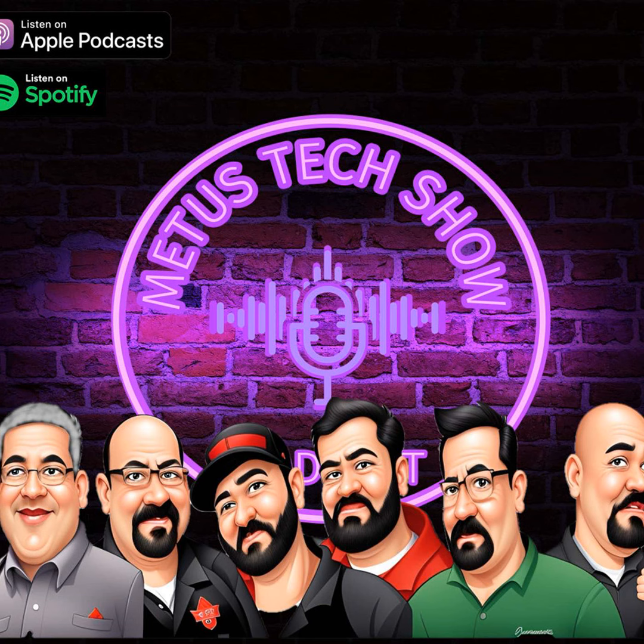Sure. So as you mentioned, that fan, that's a great one. For someone who's new to a ductless offering, that's the what, but knowing the why, having the right technician, the right training, and being able to establish that confidence with that homeowner, letting them know that, yes, this is normal operation. And the reason for it, yes, this runs the fan continuously to eliminate hot and cool spots in the room. In some instances, it's moving the air always over filters, so you're actually cleaning the air as you're doing it. There's a benefit to that happening. Yeah. And that's where the temperature is being sensed, typically at the indoor unit, not at a thermostat like a conventional system, to Bryn's point. Correct. So that question comes up quite a bit.